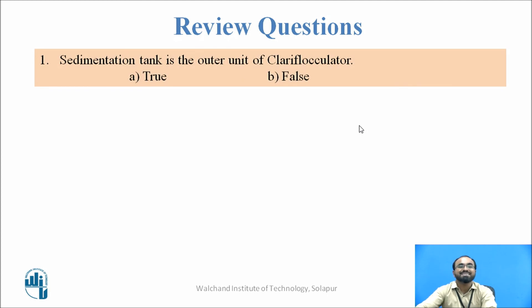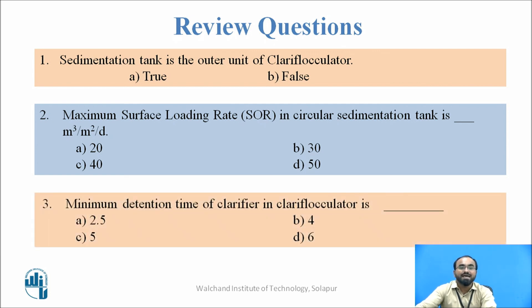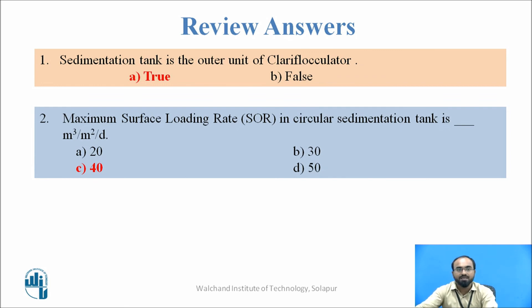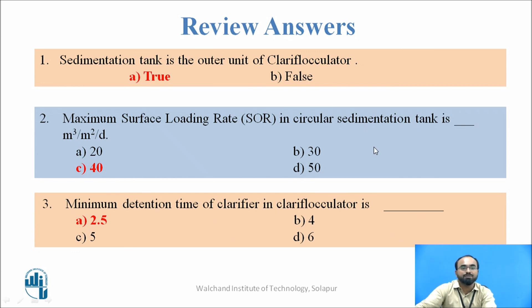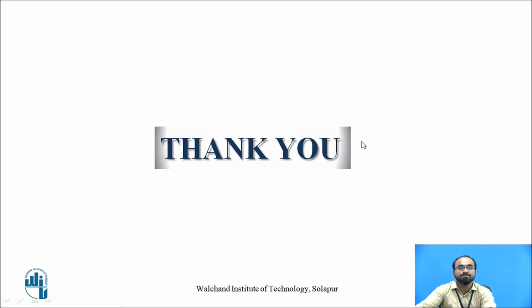Review questions: First, is the sedimentation tank the outer unit of the clariflocculator? — True. Second, what is the maximum surface loading rate in a circular sedimentation tank? — Maximum SOR is 40 m/day. Third, what is the minimum detention time of a clarifier in a clariflocculator? — 2.5 hours. Thank you.